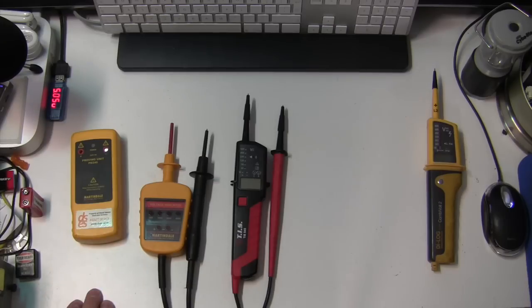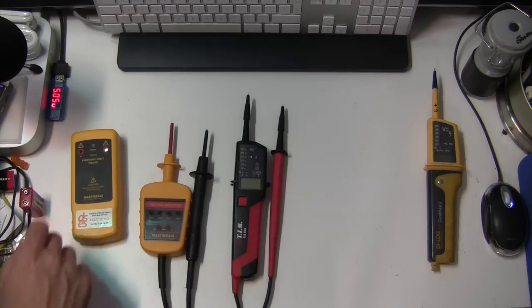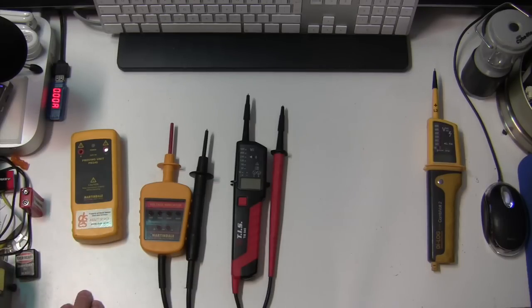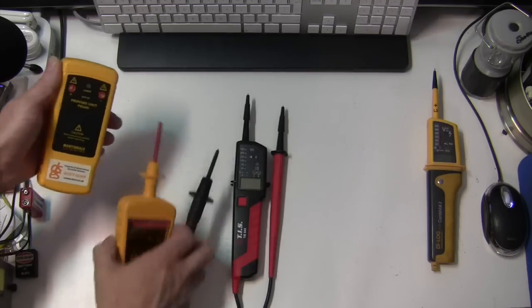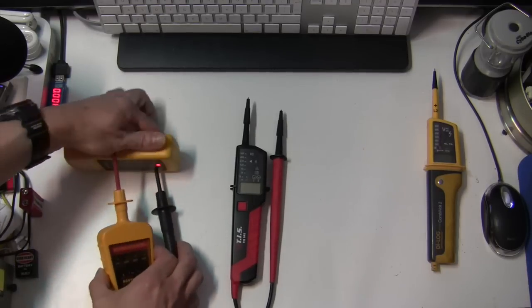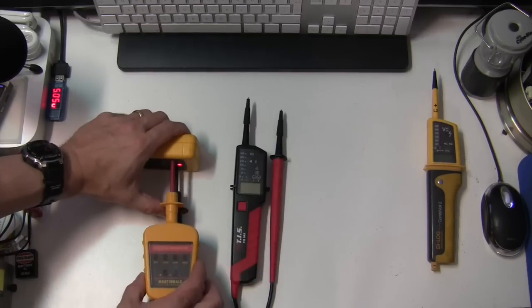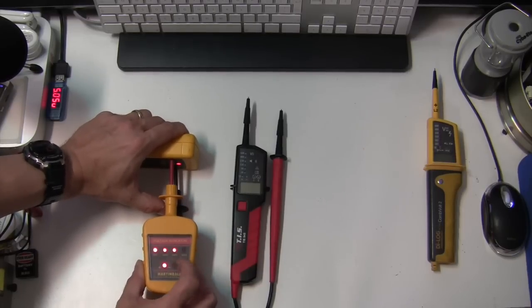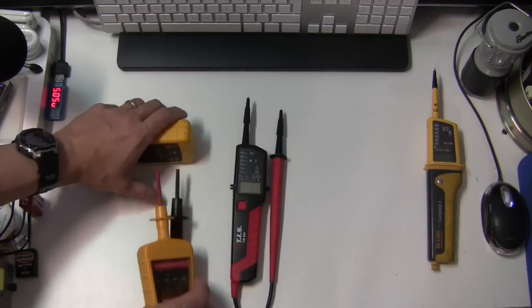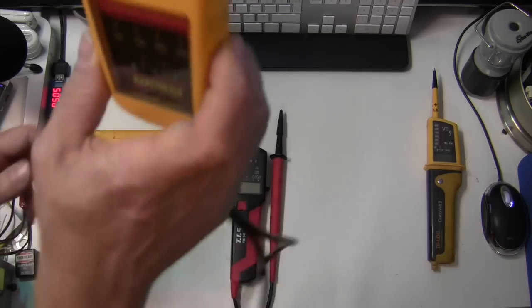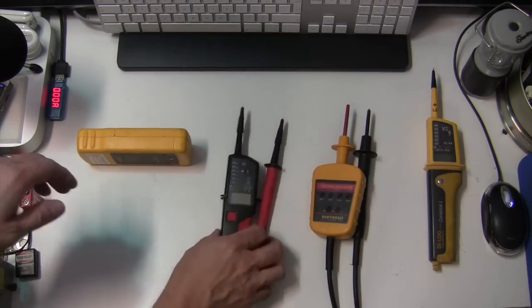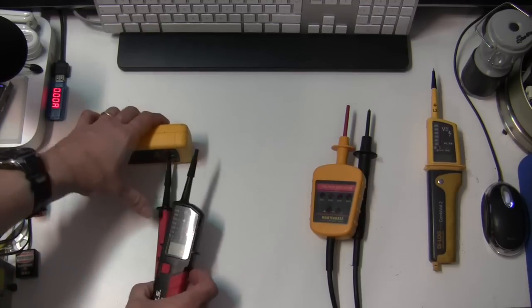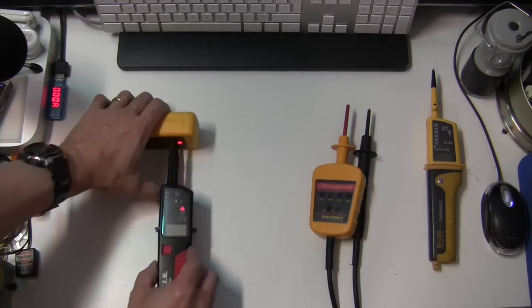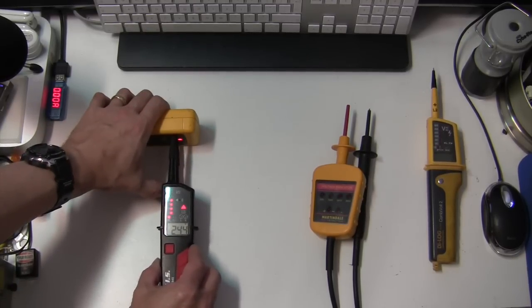This Martindale proving unit takes a 9-volt PP3 battery and will put out 250 volts DC. So if I take my testers and plug them in, then it should prove, at least up to the 250 volt lights, that my tester is working okay. Let's just do that with the TIS one as well. And sure enough, there we go.